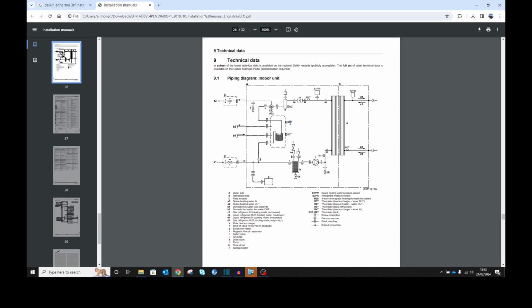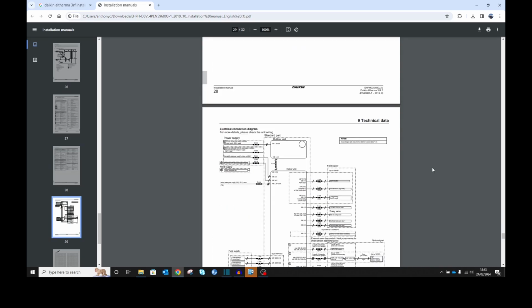You'll also note we've got thermistors for the top and the bottom of the hot water cylinder, and we have got the cold water inlet and hot water outlet. What you'll also notice is that we have got an expansion valve down here. So this is in addition to the expansion tanks that we've got outside the unit. There's also a magnetic filter which is in addition to the outside unit. I do not know what basis the plumbers have for requiring an extra expansion tank in addition to this one, but I suspect they've done their calculations and figured out that this expansion tank is probably insufficiently sized for the job. So this is the piping diagram.